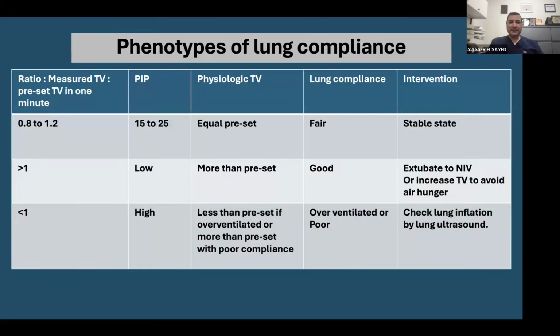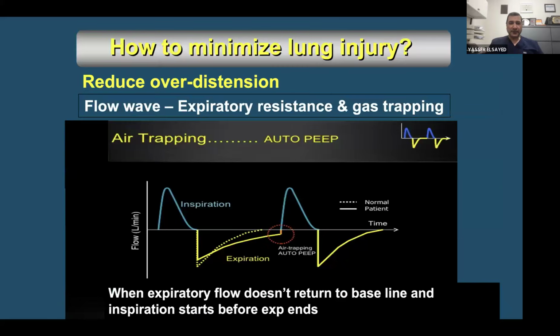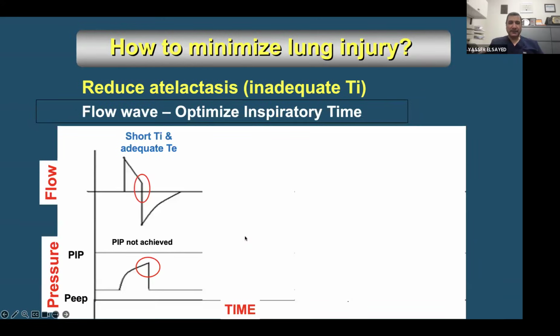And simply you can assess that by looking at the curve. Just go back to the curve here. So once you see the expiration doesn't go back to zero, that could be either because of air trapping or because of higher resistance. So you need to decrease the I time and give more time, or decrease the rate to give more time for expiration. That's one of the applications for time constant. The other application is that there is not enough time for inspiration to go in. So you need to increase the I time to get all of the volume or all of the pressure needed to match the target.